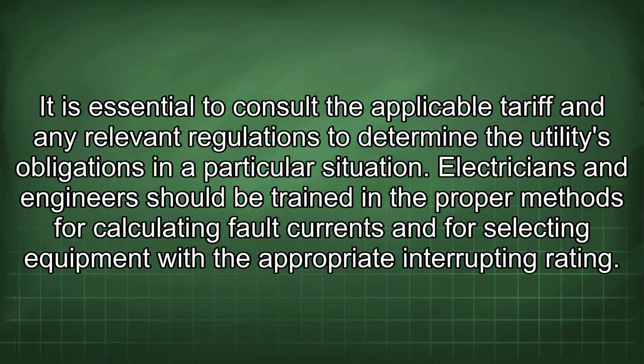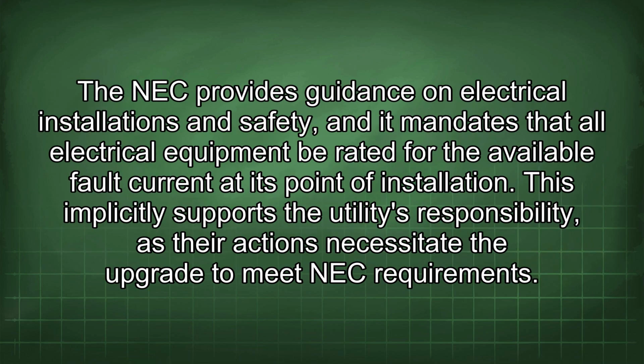It is essential to consult the applicable tariff and any relevant regulations to determine the utility's obligations in a particular situation. Electricians and engineers should be trained in the proper methods for calculating fault currents and for selecting equipment with the appropriate interrupting rating. The NEC provides guidance on electrical installations and safety, and it mandates that all electrical equipment be rated for the available fault current at its point of installation. This implicitly supports the utility's responsibility, as their actions necessitate the upgrade to meet NEC requirements.